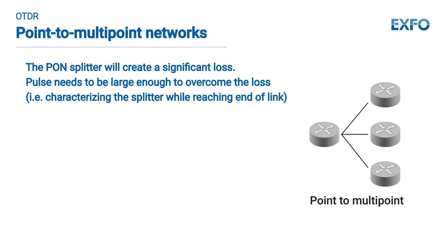For point-to-multipoint networks, the PON splitter will create a very significant loss. The light is split into equal parts depending on the splitter ratio, so each individual branch has, in a 1 by 32 splitter, only 1/32nd of the total power — a huge loss for any OTDR test. The pulse should therefore be large enough to overcome this big loss, to characterize the splitter while reaching the end of the link.